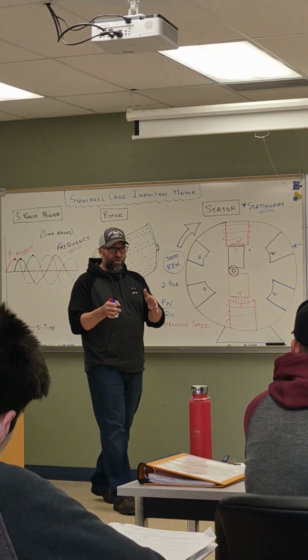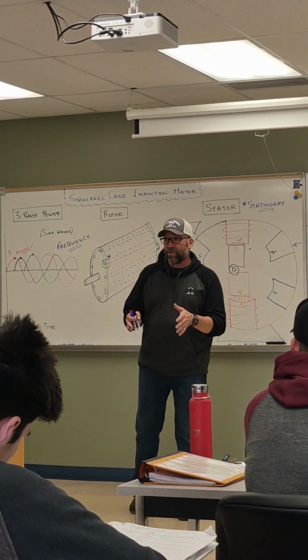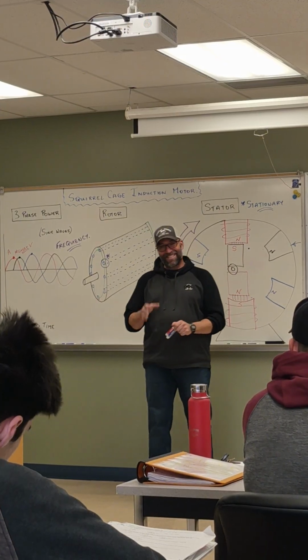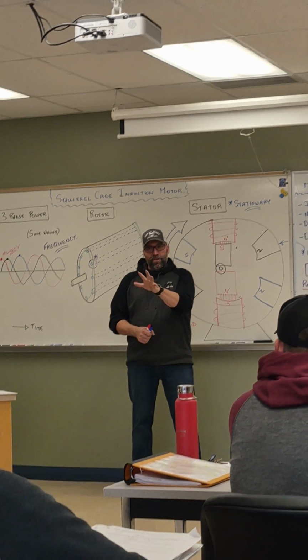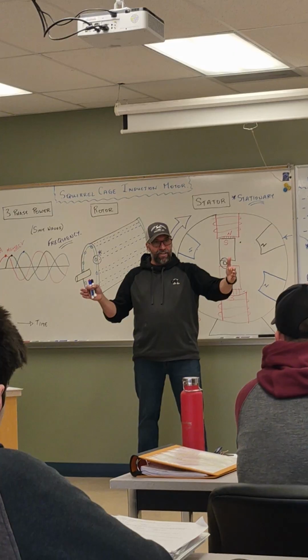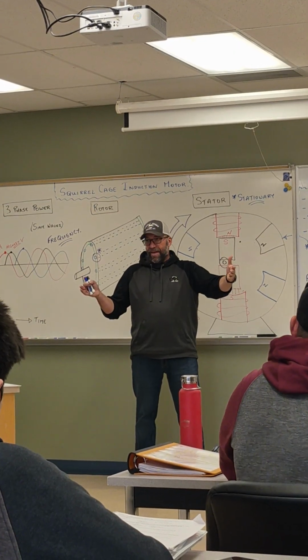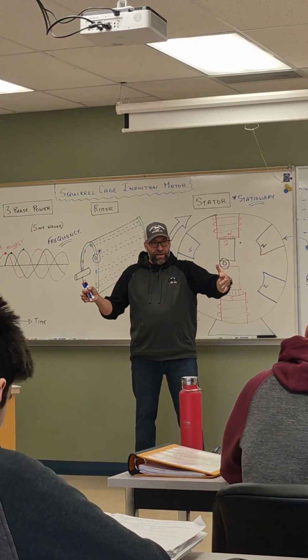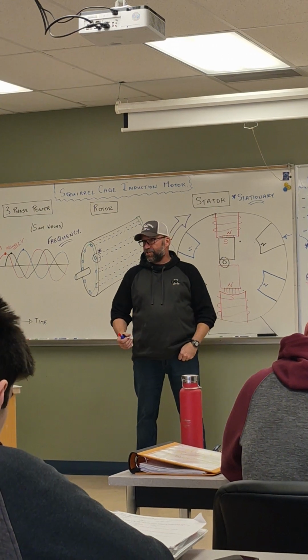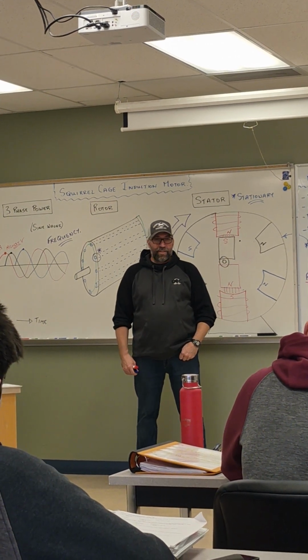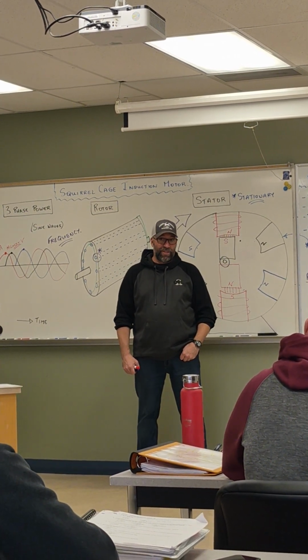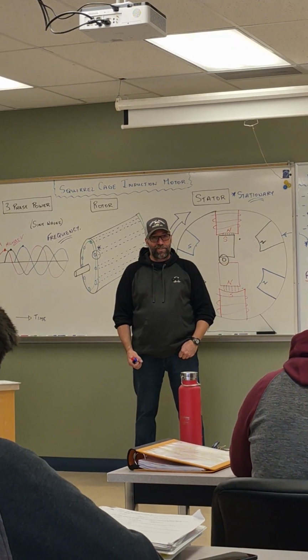It is exactly the RPM of the frequency that you feed it. So now for finite control, really important control, synchronous motors are the best, because you know exactly how fast it's turning. You know that if it's turning 250 RPM, that is 75 linear feet of conveyor speed. That's what we need for this production number. Suddenly you know exactly the numbers. You can actually calculate off of it. Squirrel cage you can't. But squirrel cage is cheap and easy, so we use them all the time.